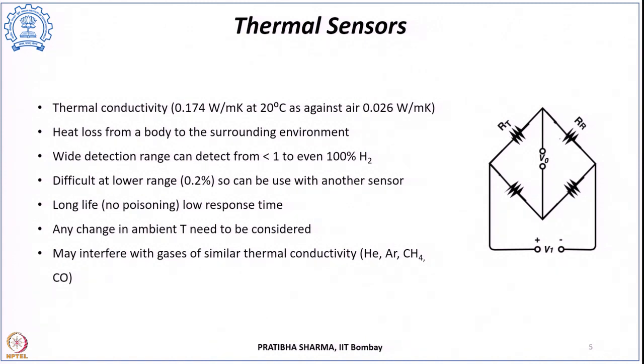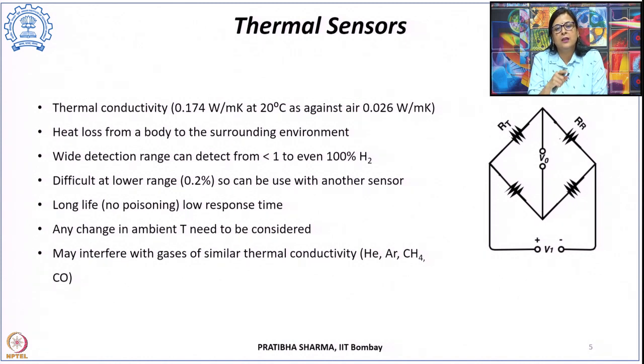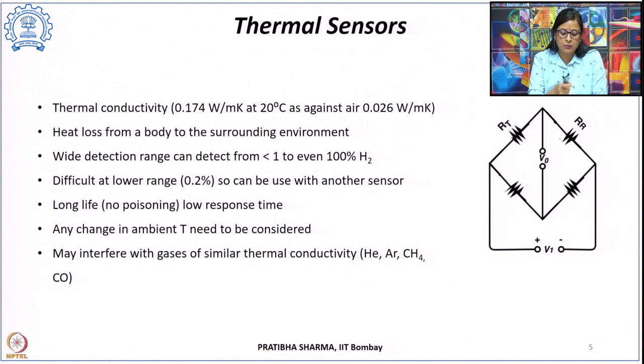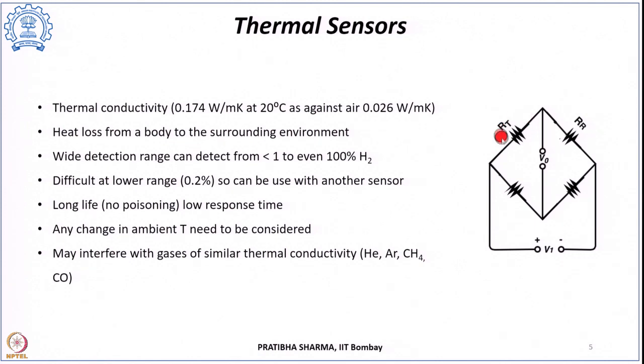If there is more hydrogen in the environment, heat dissipation increases because of hydrogen's higher thermal conductivity, and that correlation is used to find the hydrogen concentration. These thermal sensors typically consist of two resistors — a target gas resistor and a reference resistor — housed in a target cell and a reference cell respectively, connected in a Wheatstone bridge.